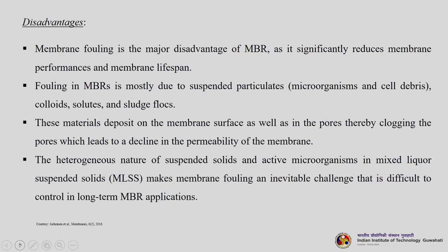So, the fouling of the membrane significantly reduces the membrane performance and membrane lifespan. Fouling is mostly due to the suspended particulates, which are microorganisms and cell debris, colloids, solutes and sludge flocs. These materials deposit on the membrane surface as well as in the pores, thereby clogging pores, which leads to a decline in the permeability of the membrane.